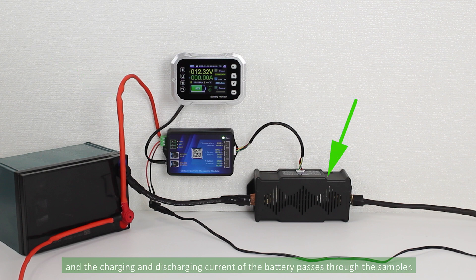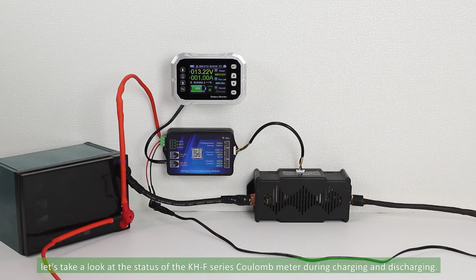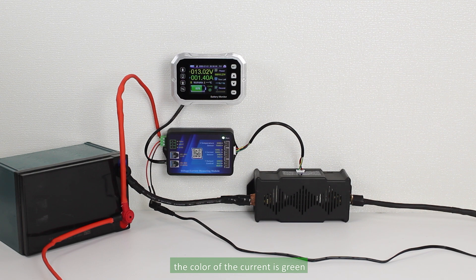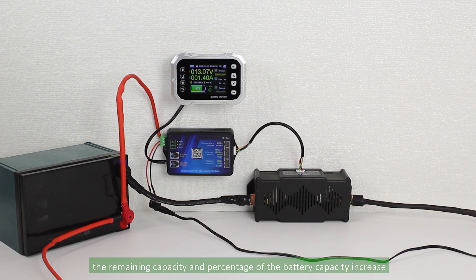Finally, let's take a look at the status of the KH-F series Coulomb meter during charging and discharging. When the battery is being charged, the color of the current is green, the remaining capacity and percentage of the battery capacity increase, and the estimated time indicates how long it will take to fully charge the battery.